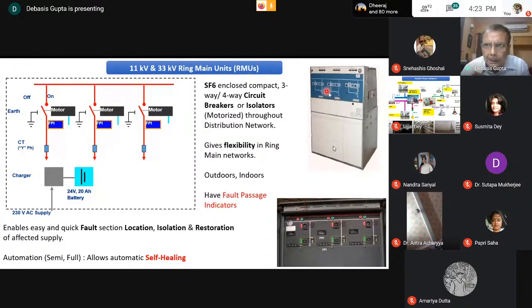What does it have inside? This is an SF6 filled cubicle. It has a bus bar, say 11 kV, but also available for 33 kV. Then you have 3 feeders coming out, sometimes 4, so it's called 3-way or 4-way. The main element in each of these legs is either a circuit breaker or an isolator.